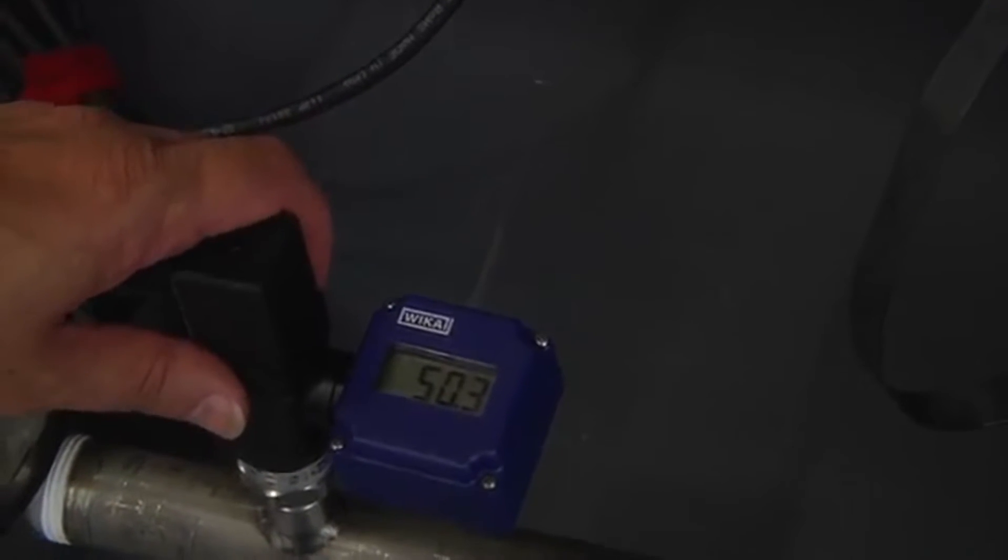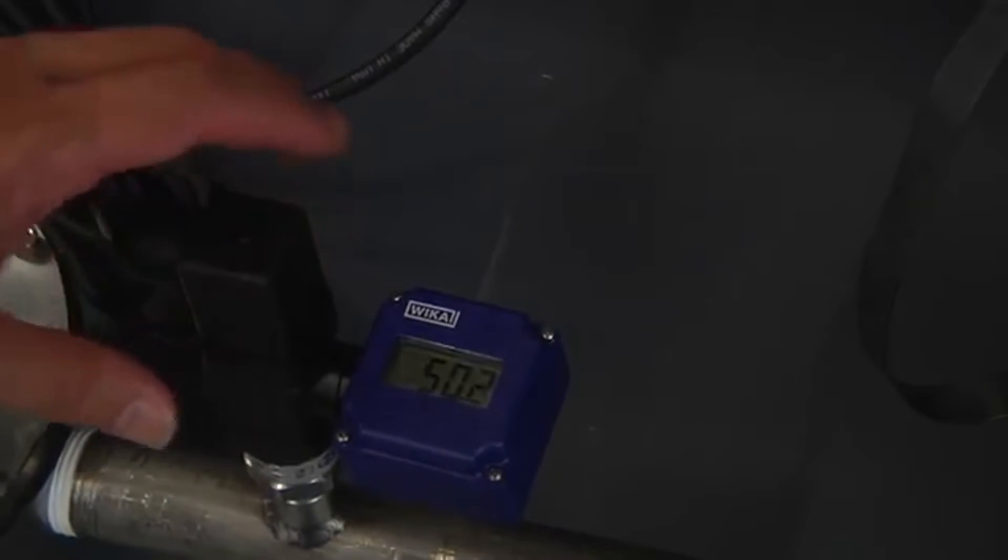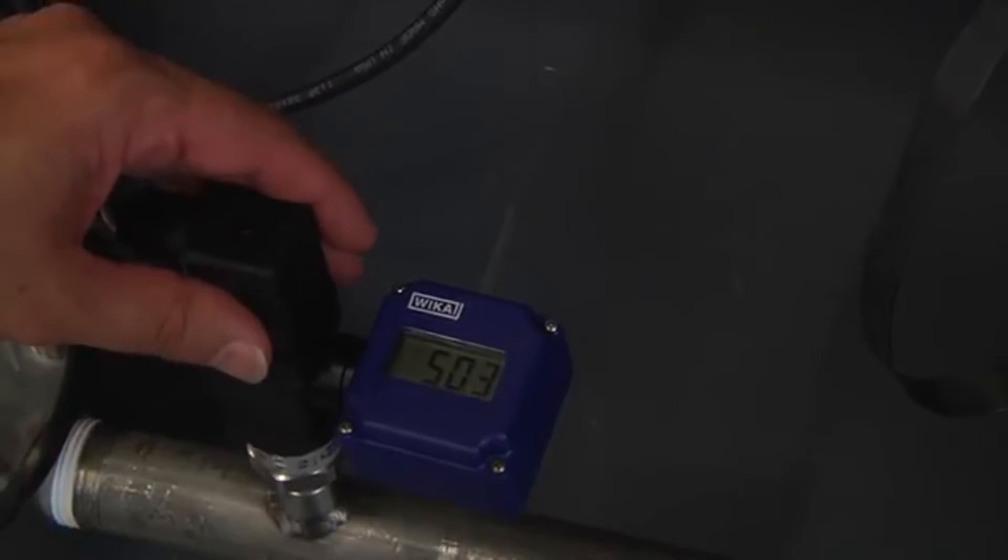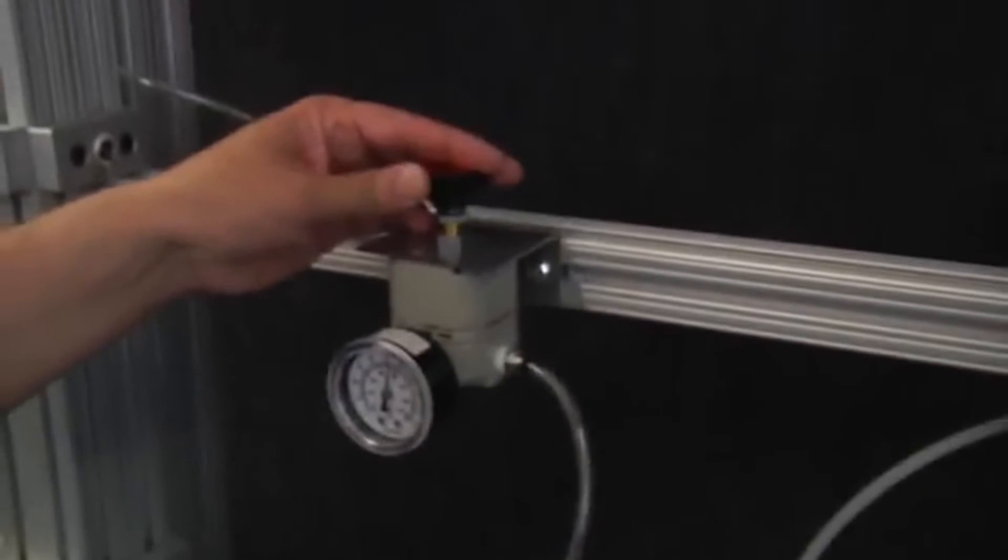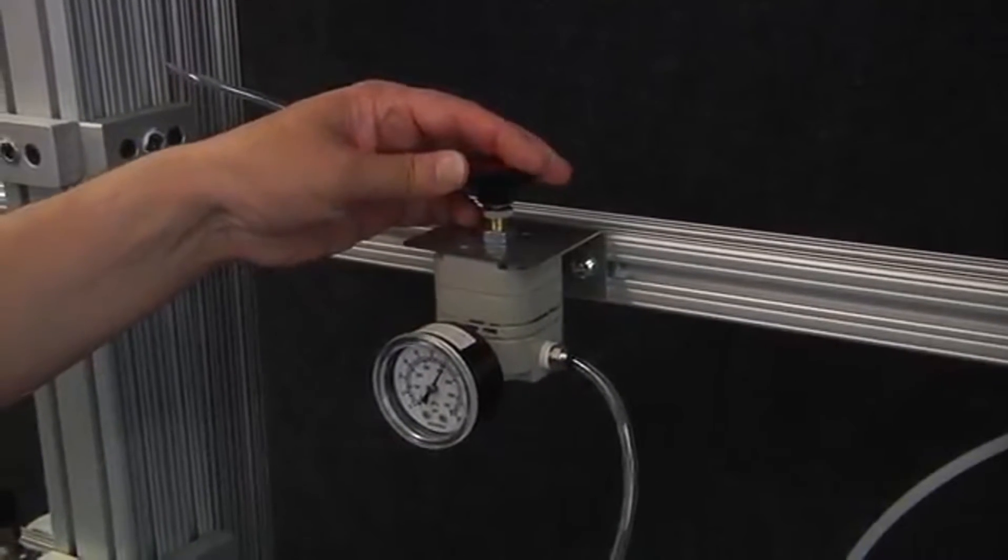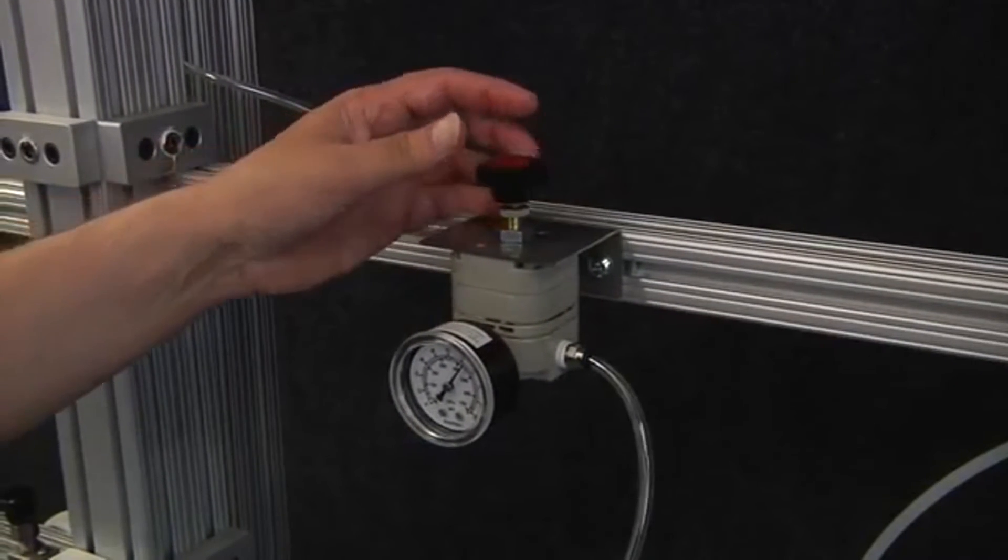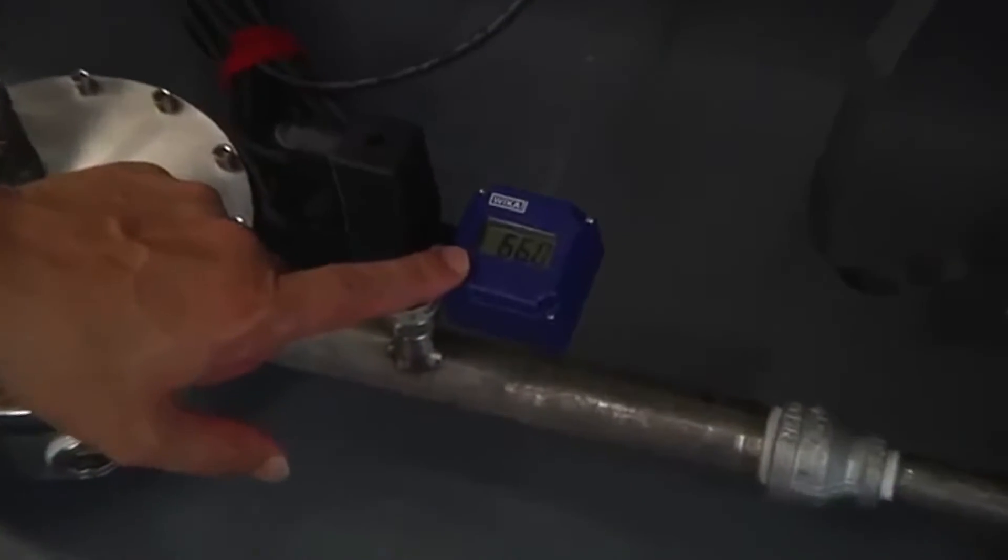And now to show the repeatability, I'm going to adjust the pilot pressure on the Equilibar Back Pressure Regulator to get something more like 65 psi on the pump curve. That's going to give us a much lower flow rate. So I'll run this pressure up to about 65. And what we'll see is when we have 65 psi on the output of the pump, that the flow meter is at a much lower value.